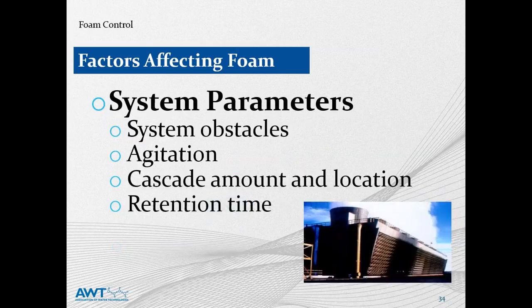Moving to system parameters: as you consider foam, look at system obstacles. Are there weirs or other obstacles that the product will have to pass either over or under? Is there agitation, and how much? Where does it occur? And then cascading — water falling will create turbulence which then will create foam. And lastly, think about retention time: how long is the water actually in the system? Is the water in a small holding tank for a limited period of time, or are we addressing foam in a lagoon where the water remains captive for a long period of time?